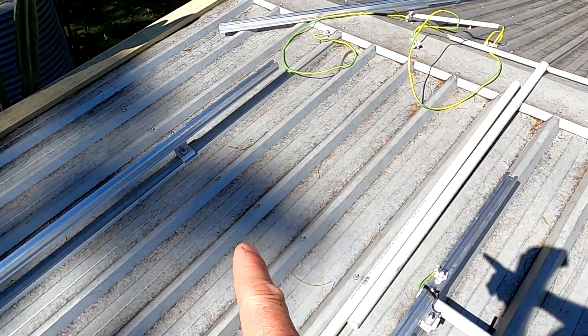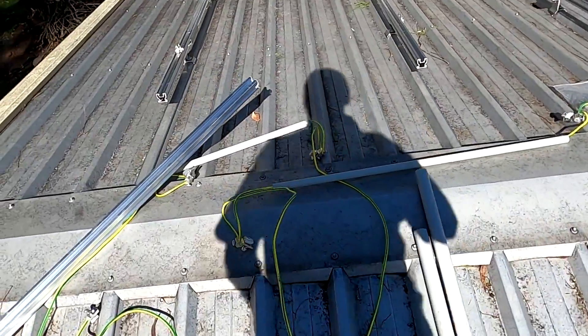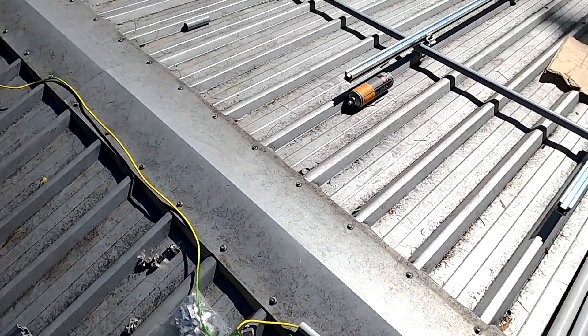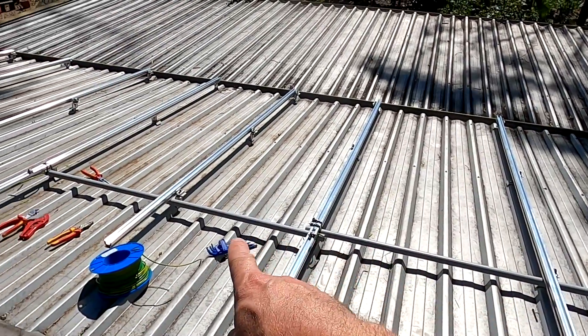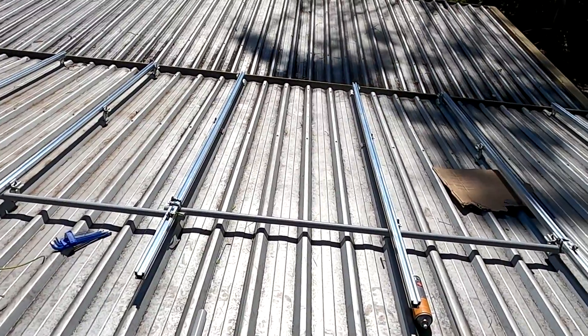So as you can see here, they are grounding or earthing only every second rail, not every one as we did before - see here, still my old cable. You can see I've got so many clamps on there because I basically earthed all of the rails, but they do only every second. That's all it needs. And that's actually a good idea to put this conduit underneath the panels, put your earth cable through it, and then you can feed your solar cables as well through it, and then they go down into the roof.